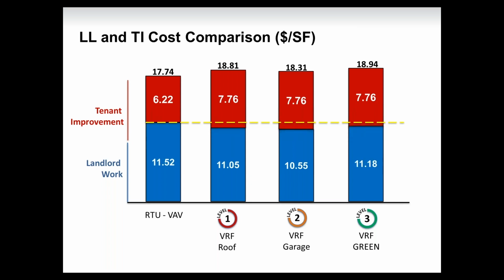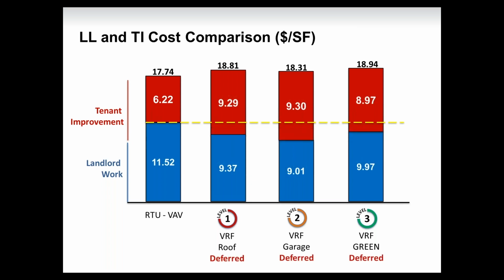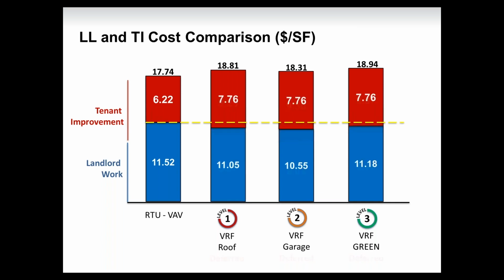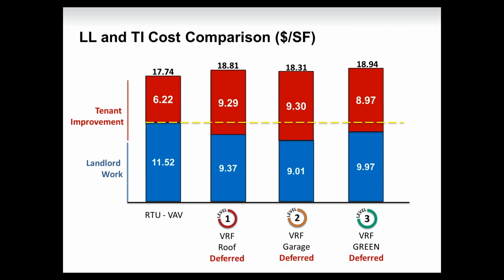One thing we also haven't talked about here is what we've called a deferred cost, which is another option for a developer to save even more money. We were talking in the previous slide about 1105, 1055, and 1118. By deferring the cost, the owner can save even more money. The way we're thinking about doing the deferred cost is that most people look at an apples to apples comparison of VRF against VAV rooftops, matching tonnage for tonnage. So for this example, you have 210 tons of rooftop, all in the shell cost, and 210 tons, or 216 in our case, of VRF. This really isn't the most cost-effective design or the most aggressive way to minimize the developer's cost.